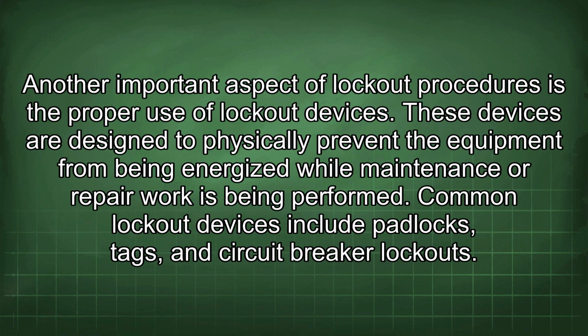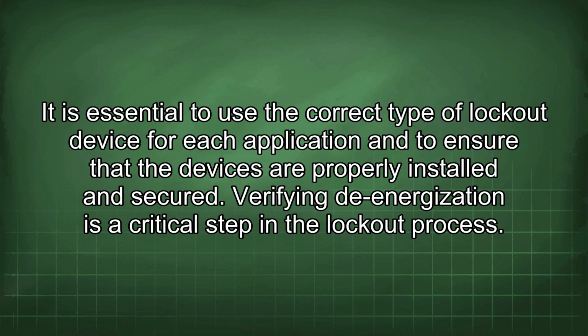Another important aspect of lockout procedures is the proper use of lockout devices. These devices are designed to physically prevent the equipment from being energized while maintenance or repair work is being performed. Common lockout devices include padlocks, tags, and circuit breaker lockouts. It is essential to use the correct type of lockout device for each application and to ensure that the devices are properly installed and secured.